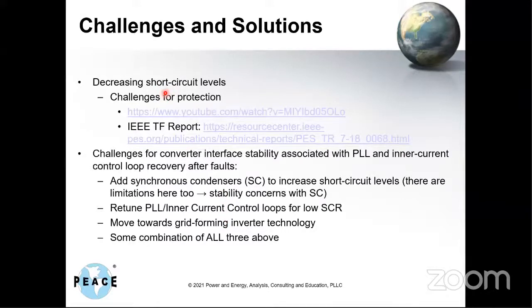As your short circuit levels decrease, protection becomes more challenging. And I'll confess, I'm not a protection engineer. I probably know enough to be dangerous. But there are reports, an IEEE report on YouTube you can go to, where we discuss that. And the issue there is obviously that because this converter-based generation is very tightly current regulated, you're not going to get, like with the synchronous generator, 3, 4, 5 per unit short circuit current.